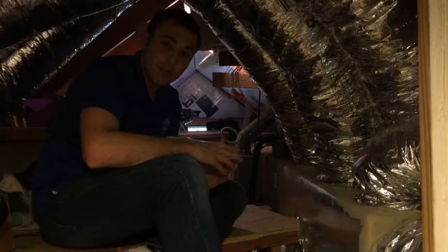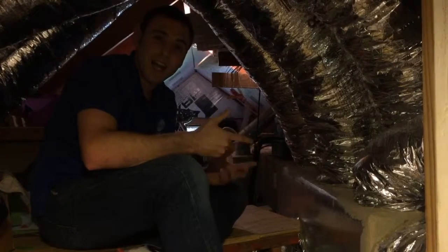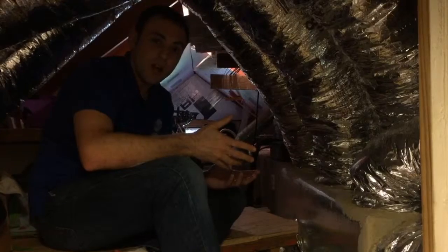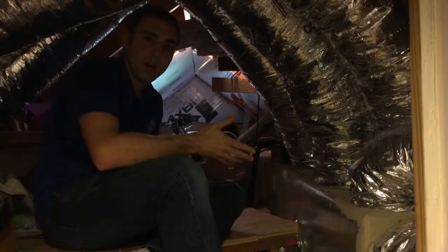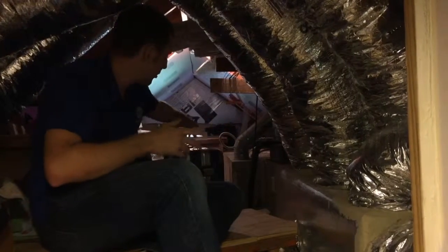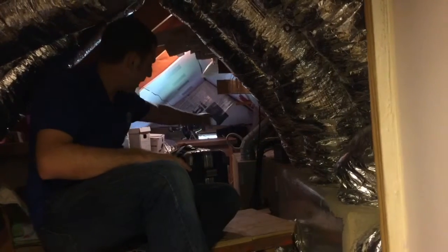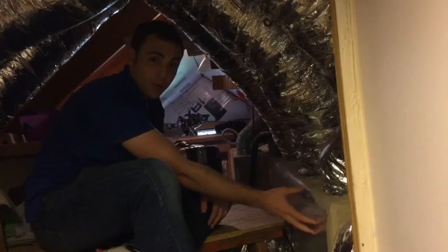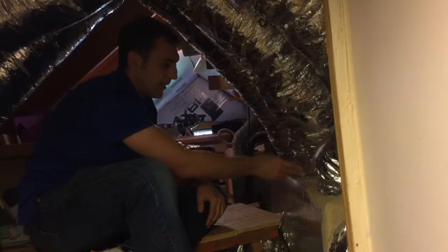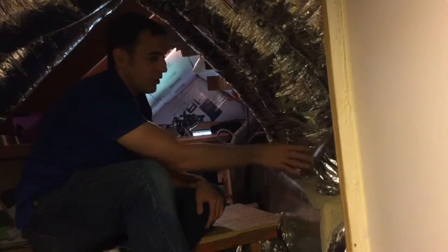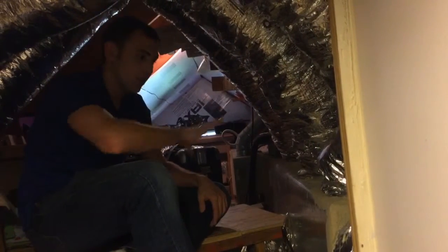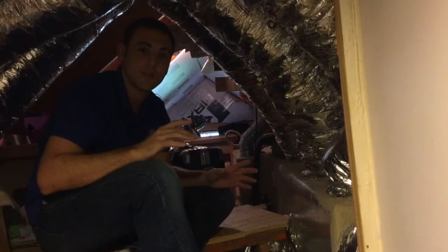So we're now looking at some ductwork, looking at duct design and how this might affect air distribution. This is a very common setup. We've got an attic unit here that's horizontal, and we've got the furnace down there, the coil here, and then this is the supply plenum. This is a supply plenum that's duct board, and it's got these starting collars that hook up to this flex duct that goes off to all sorts of different parts of the house.